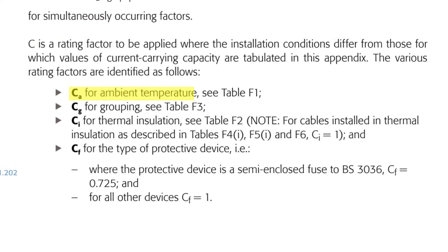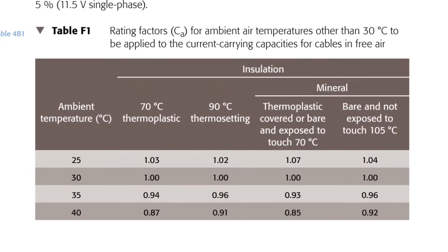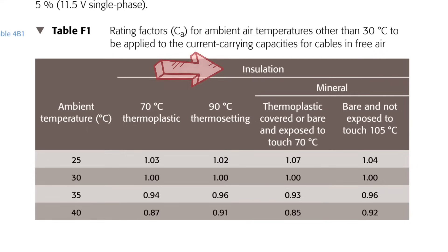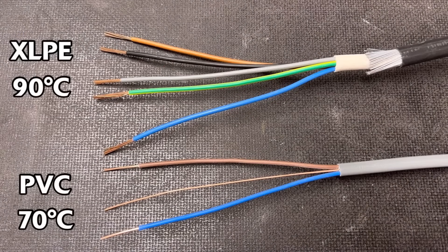CA is a factor we apply depending on the ambient temperature of the area the cable is installed in. We can find the numbers in table F1 of the on-site guide. As you can see, it's made up of five different columns in total. The first is the ambient temperature value, going up in fives from 25 degrees up to 40 degrees. The other columns relate to different types of insulation or cable — the first type is 70 degrees C thermoplastic, which is the insulation you find on PVC insulated twin and CPC cable.